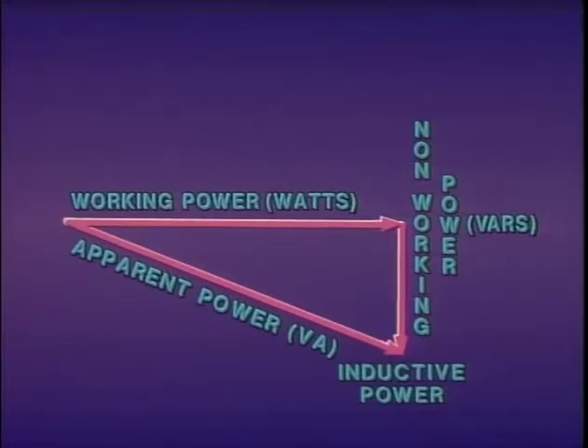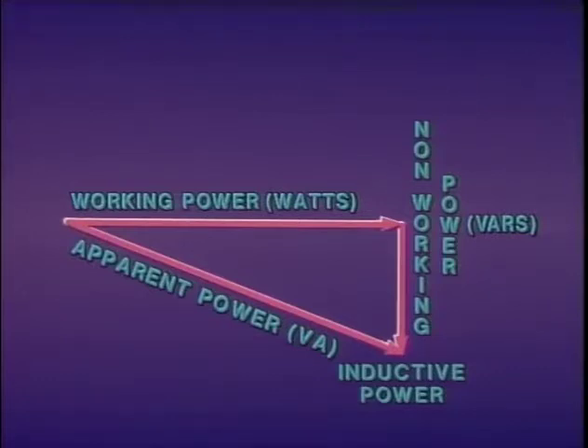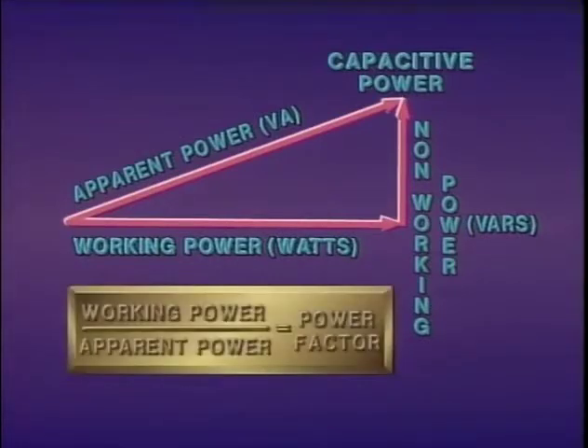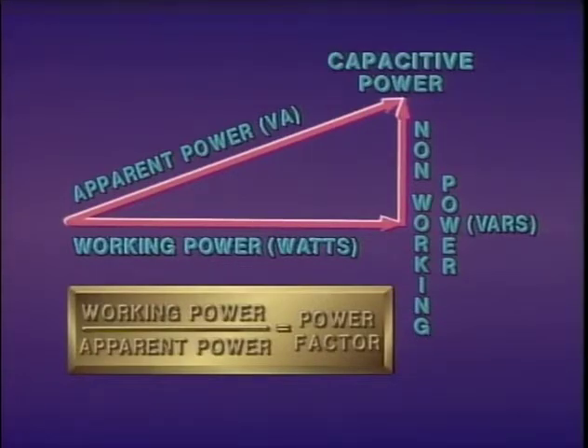Apparent power is measured in volt amperes and is represented by a diagonal line in the illustration. When a T&D system has more inductive power than capacitive power, the result is apparent power on the inductive side of working power. If a T&D system has more capacitive power than inductive power, the result is apparent power on the capacitive side of working power. The ratio of working power to apparent power is commonly referred to as the power factor. Capacitor banks and shunt reactors are used to improve the power factor — to improve the ratio of working power to apparent power.